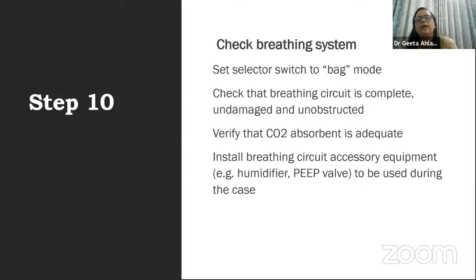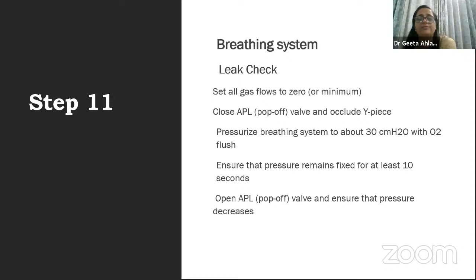CO2 absorbent should be thoroughly checked. When was it changed? What about the color coding? Install every breathing circuit accessory. Have your checklist ready and ensure every resource you have. Leak checks, again, as I told you: with the APL valve, you should pressurize your breathing circuit to about 30 centimeters. Your APL valve should not pop off, and then when you release it, the pressure should fall immediately.